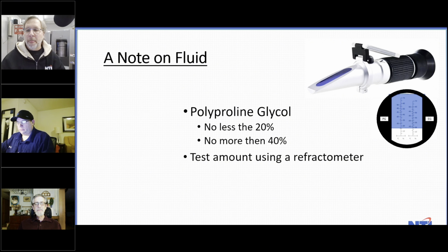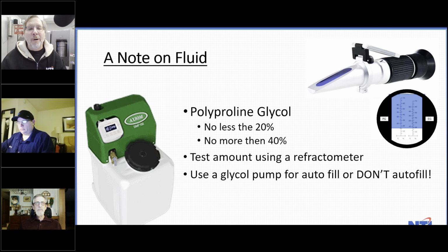Be aware of that. Next, use a glycol pump if you want an autofill. Do not use a water autofill on glycol on a snowmelt system, because it will screw up your amounts of glycol and freeze that system in a minute.